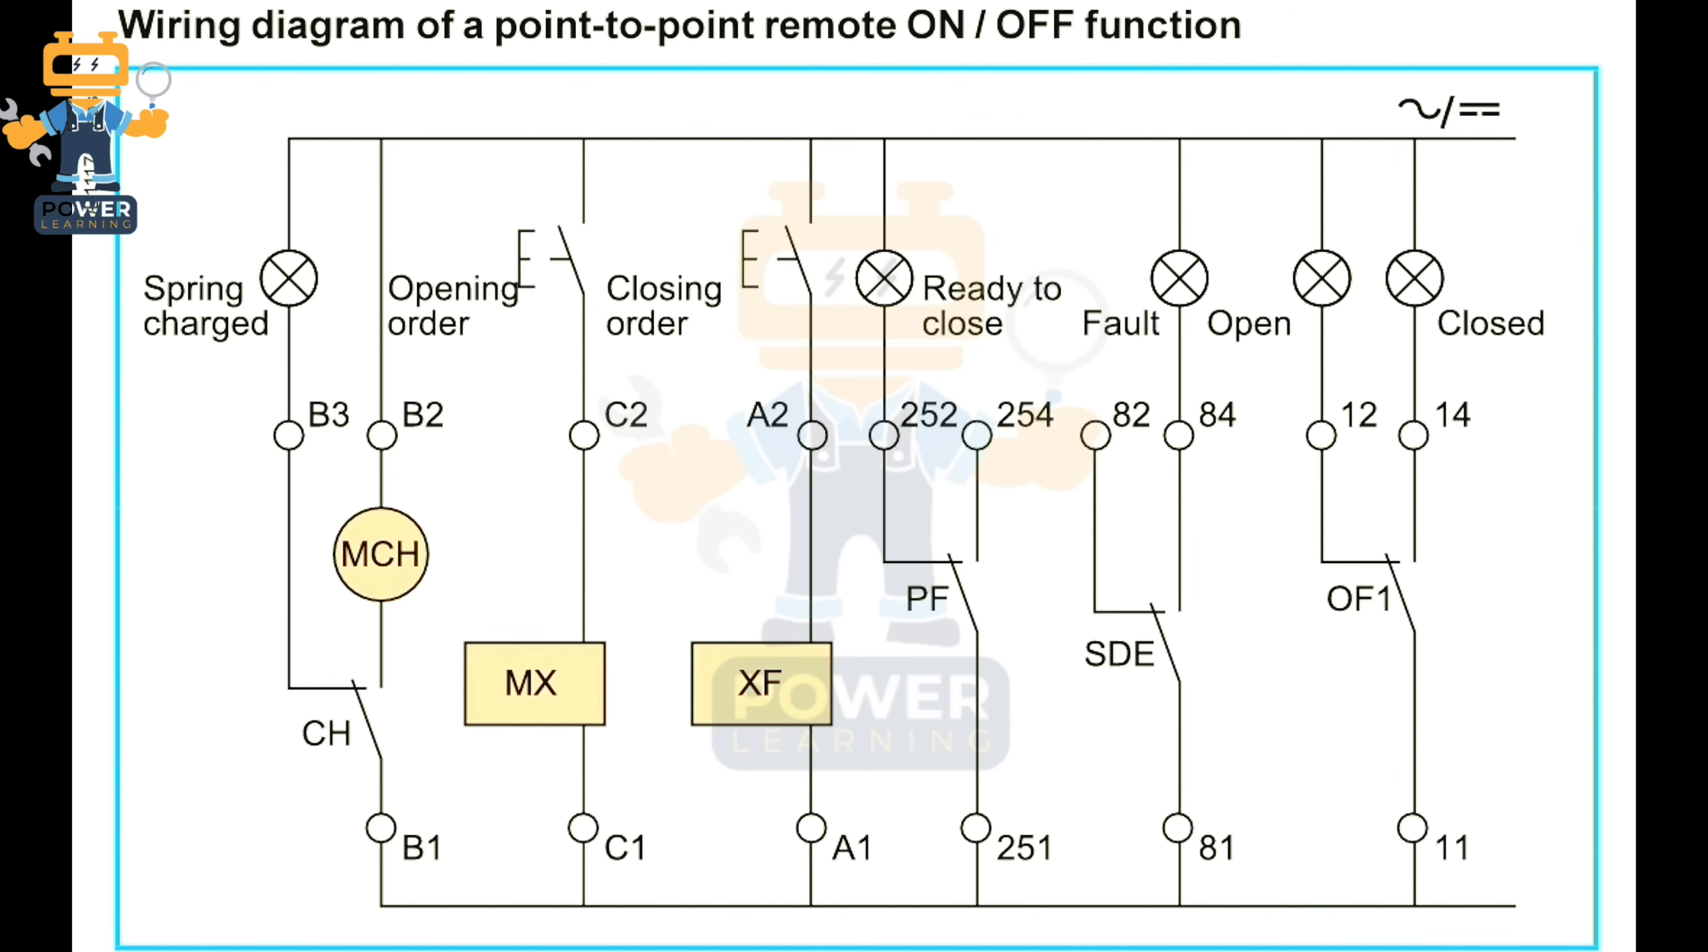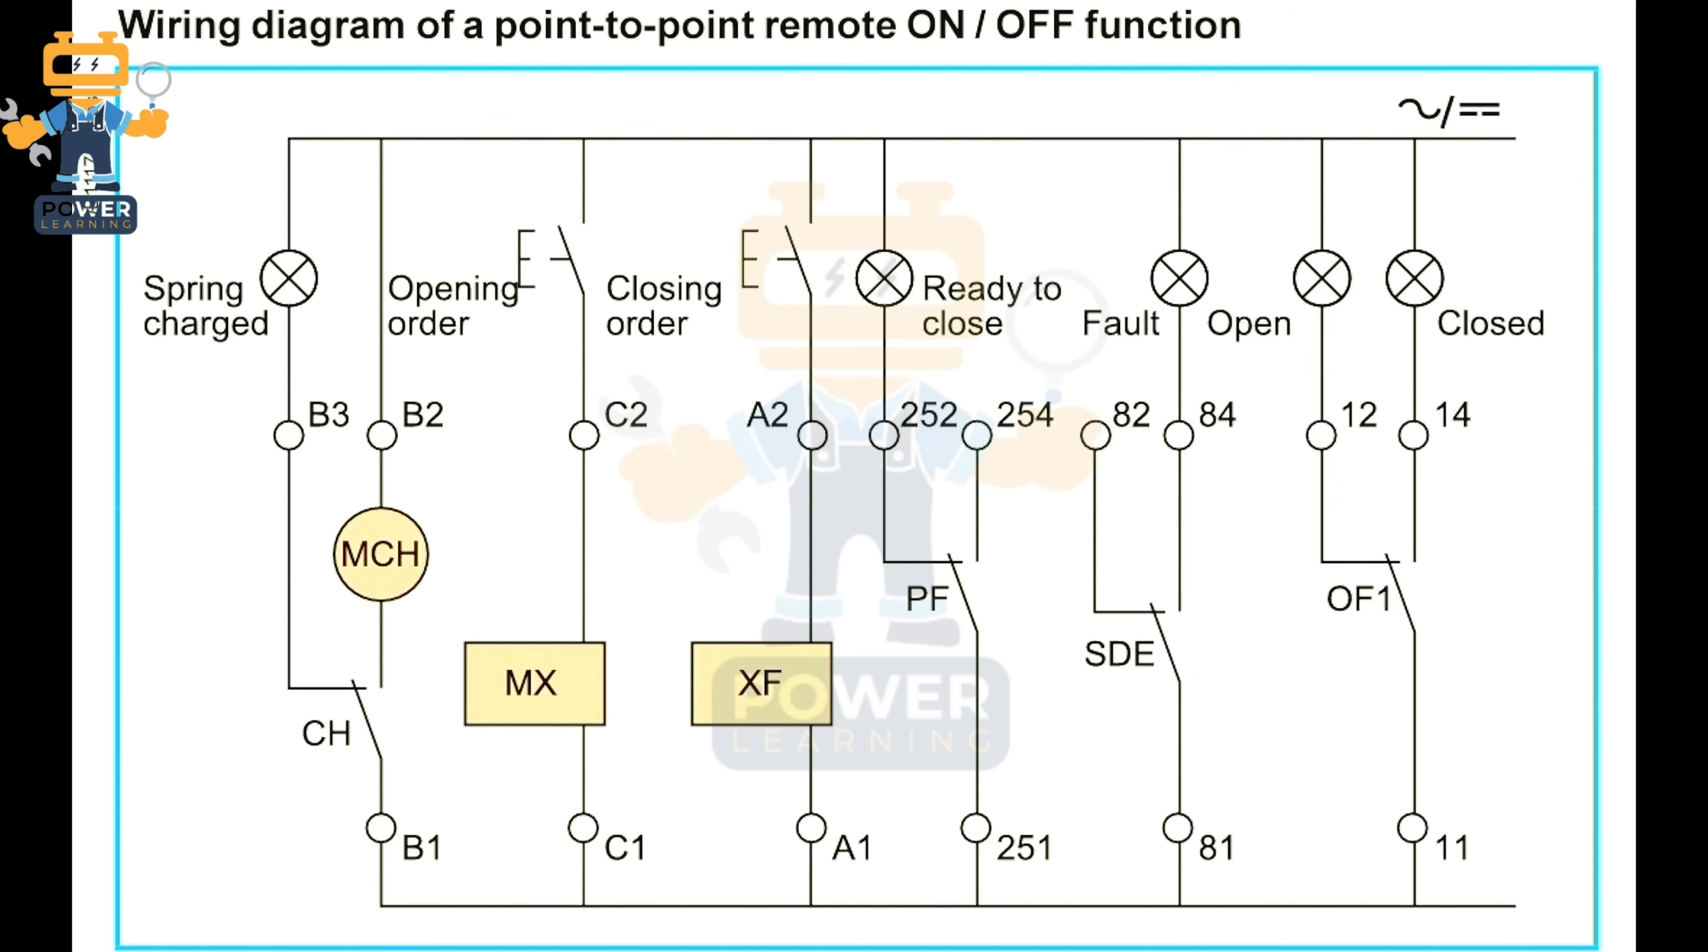Other than this we have OF1. OF1 is an auxiliary contact. Auxiliary contact we will use in many applications, but here to explain simply, we use it for breaker opening and closing status. If the breaker is open it will show us on the indication lamp that the breaker status is open. Once the breaker is closed, this normally open contact will get close between 11 and 14, so it will show the indication that the breaker is closed.